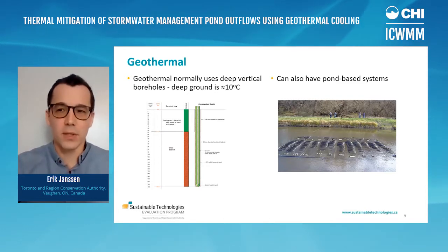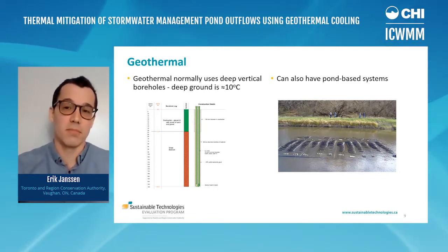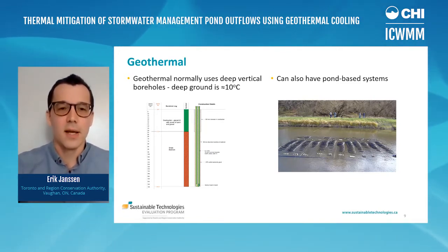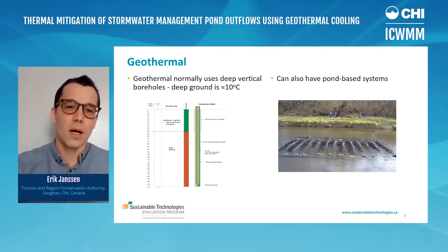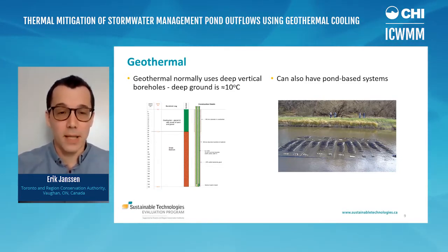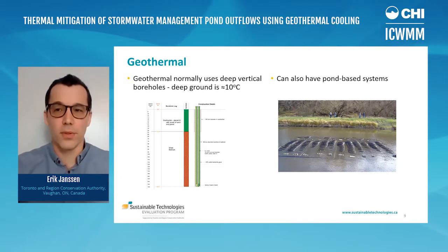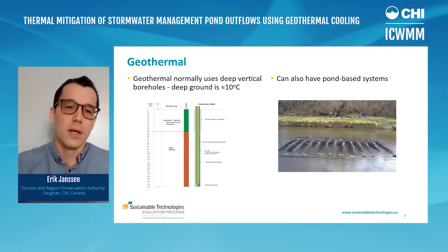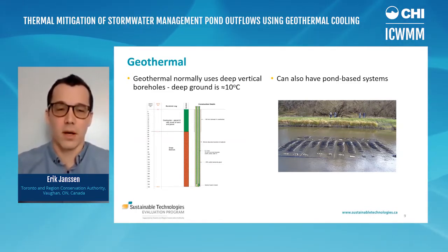Essentially, you have a drilling rig. It bores a hole maybe about 5 inches diameter deep into the bedrock. Common depth for large buildings in the area of Toronto is 600 feet. Inside of that borehole, a U-bend of plastic pipe is placed, and then the whole thing is backfilled with a thermally conductive grout. So what happens is there's a heat transfer fluid. It goes down one side of that pipe in the borehole, goes all the way down, and then comes back up again. And you get heat transfer between that fluid and the ground, depending on the temperature difference.